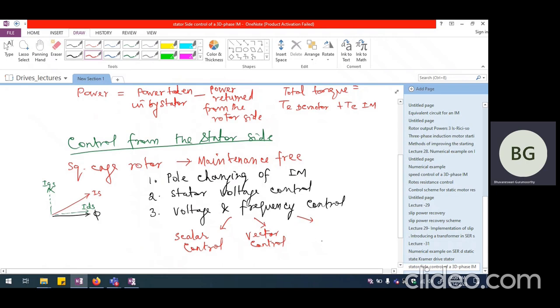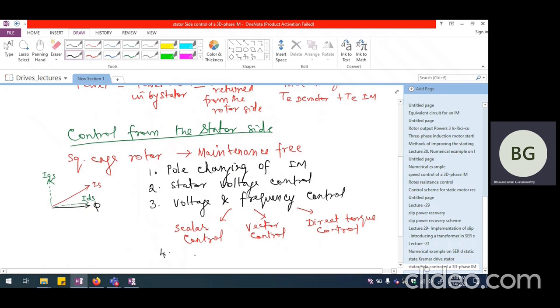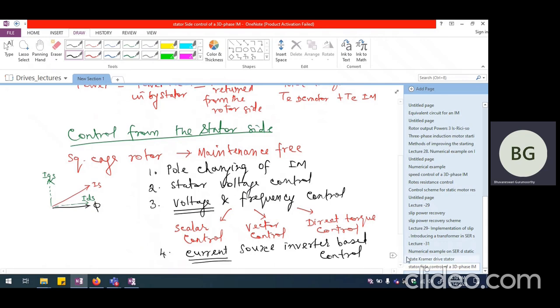The third method, which came up about 40 years ago — in 1984 — is generally known as direct torque control, which is being sold as a very successful drive by ABB. We will be looking at direct torque control as well. One more method we will look at is current source inverter based control. When we talk about voltage and frequency control, we are applying a particular value of voltage without direct control over the current. Current source inverter based control is generally used in extremely large rated drives — megawatt level drives — where a current source inverter can directly feed such drives with various advantages over voltage control drives.